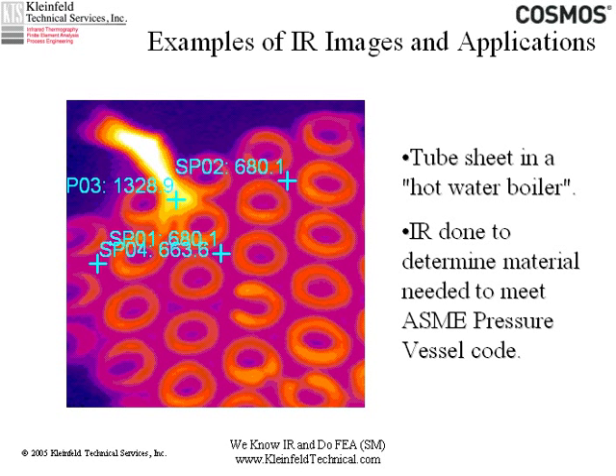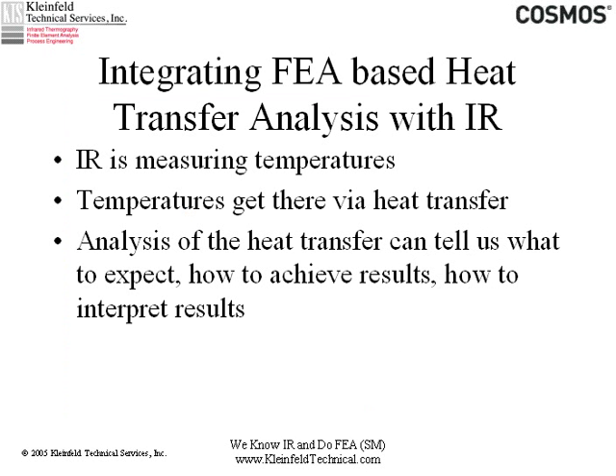Examples of infrared images from an engineering application: you're looking at a tube sheet in a hot water boiler. You've got gas coming out of the holes, a flame combustion system up above. You can see a thermocouple has been mounted — not properly for good measurement, by the way. You can see at the crosshairs temperature measurements in Fahrenheit in the mid-600 Fahrenheit range. This was then used as part of an ASME pressure vessel code validation on a new boiler design — they needed to know what metallurgy would be required, so we were able to measure it here.